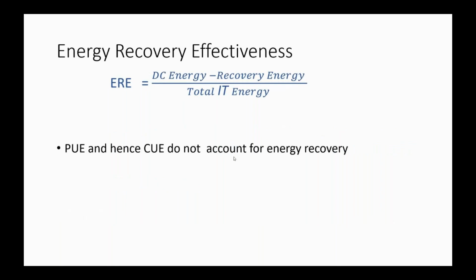The other thing with both PUE and CUE is that they are rooted in the past. These days there is such a thing as energy recovery. The side effect of a data center is heat, and these days there is a lot of heat recovery options to reuse that heat. There is no credit given for reusing that heat in PUE or CUE. So in some sense, it's not a fair metric, because it just penalizes you regardless of what you do.